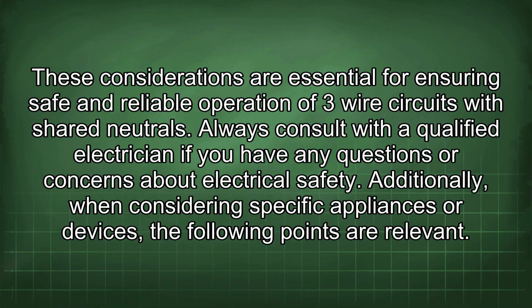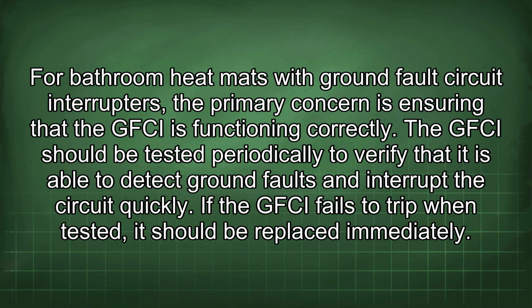Additionally, when considering specific appliances or devices, the following points are relevant. For bathroom heat mats with ground fault circuit interrupters, the primary concern is ensuring that the GFCI is functioning correctly. The GFCI should be tested periodically to verify that it is able to detect ground faults and interrupt the circuit quickly. If the GFCI fails to trip when tested, it should be replaced immediately.